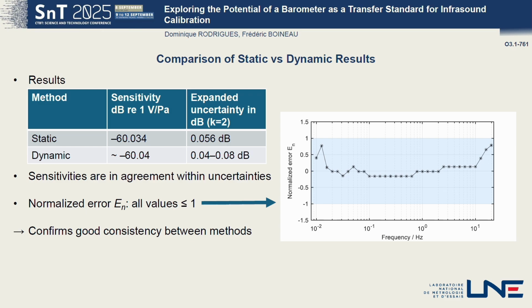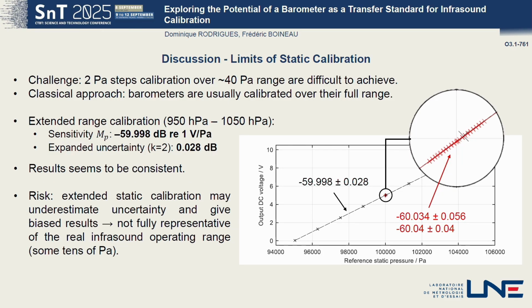Just before concluding, I would like to discuss an extra piece of information regarding a potential limit of the static calibration. The fact is that calibrating a barometer with 2 Pascal steps over a 40 Pascal amplitude is very challenging, and this is not a classical, usual calibration service provided by the static pressure labs. The usual approach is instead to calibrate the barometer over its full range. This is why, when we buy a new barometer, or if you ask for a usual calibration service, you will obtain this kind of results.